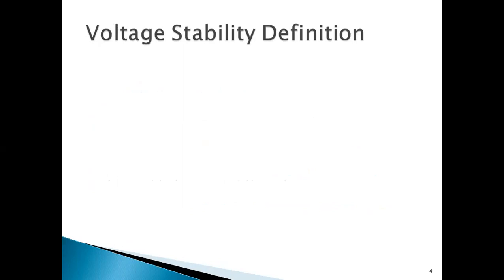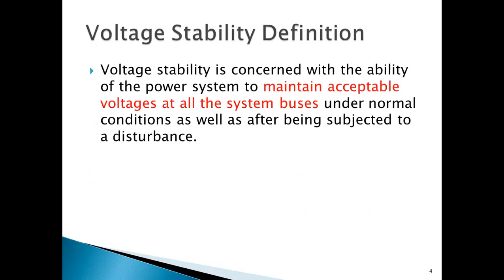Now let me discuss how voltage stability is defined. As you see here, it deals with the capability of a power system to maintain allowable voltage levels at all nodes or buses under normal and post-disturbance operations. The allowable voltage level is plus or minus 5% of nominal voltage, i.e., 1 per unit. Therefore, the range of acceptable or prescribed voltage limits is 0.95 per unit to 1.05 per unit. If the voltage is less than 0.95 per unit, it is termed as low voltage; if it is greater than 1.05 per unit, it is termed as over voltage. Voltage stability deals with ensuring that voltage magnitudes of all buses are within the prescribed limits; if not, the power system is voltage unstable.